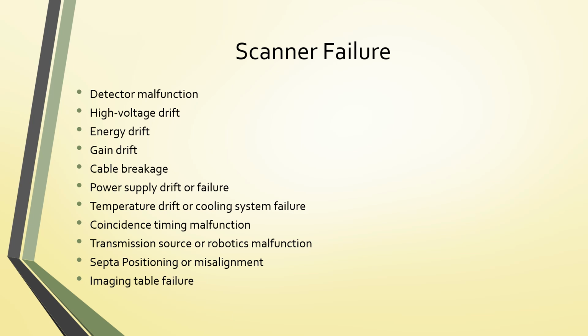So if you're having trouble with the QC source coming out, or a transmission source if you have a standalone PET, just keep in mind that that is a very common error. Another thing to consider is the power supply. And I want to point out that a lot of people have UPSs on their scanners. Of course, that's kind of standard now.